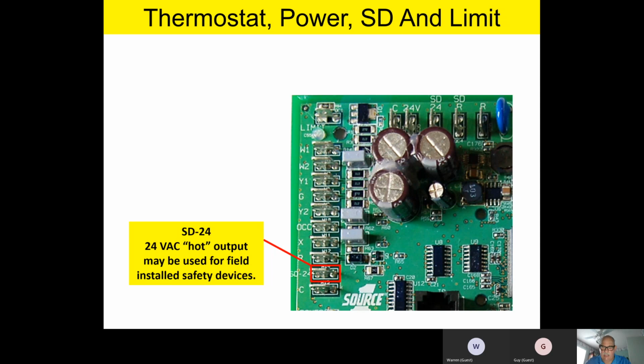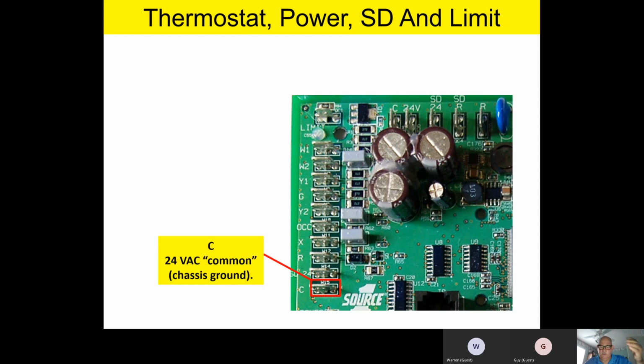Okay, and then the last terminal on our 24-volt thermostat hookup terminals is C, 24-volt common. It should be noted that we take one side of our low voltage transformer on the 24-volt side, and we take it to ground, and we call that common. So 24-volt common is actually reference to chassis ground.